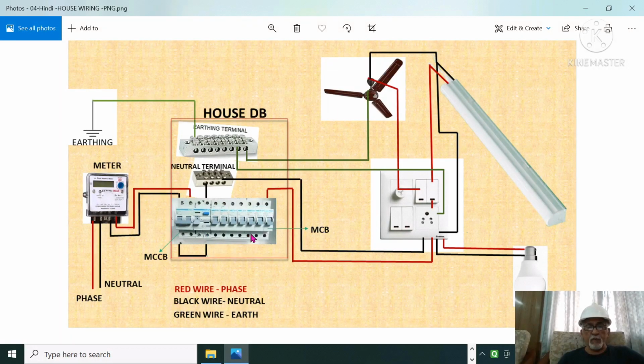These should always be looped, and from the top you can take it to different rooms. Suppose this is going to one room, and here is neutral. If you switch off this DB, main MCCB, both neutral and phase will be cut.